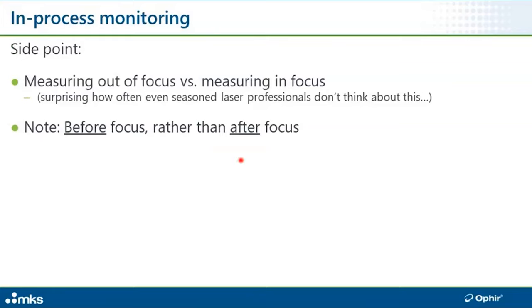As an interesting side point, everyone knows or should know to measure the power outside the focus. You don't want to measure in focus. In focus is where the power density is high enough to drill, cut, weld, vaporize, and otherwise zap your workpiece. And if you put your sensor there, then you may very likely drill, cut, weld, vaporize, or otherwise zap your sensor. Not a good thing to do. It's the same number of watts out of focus as in focus, but certainly not the same number of watts per square centimeter.